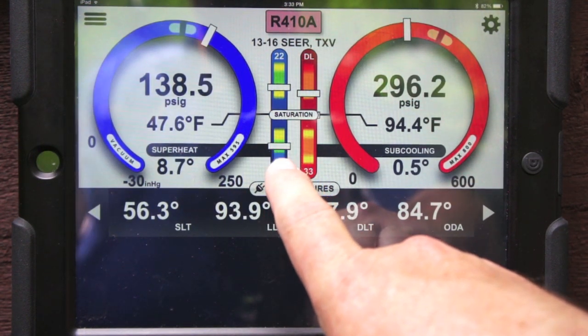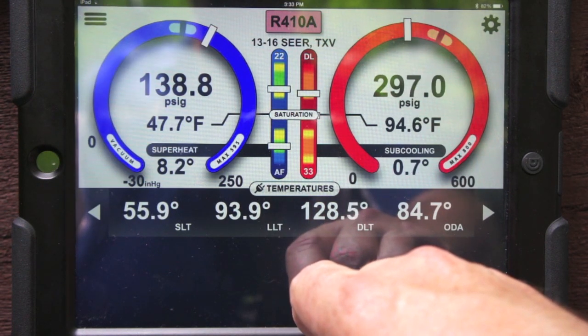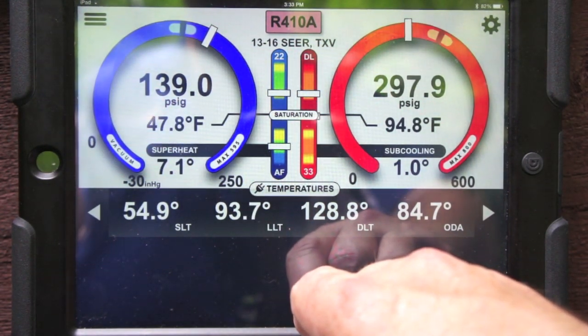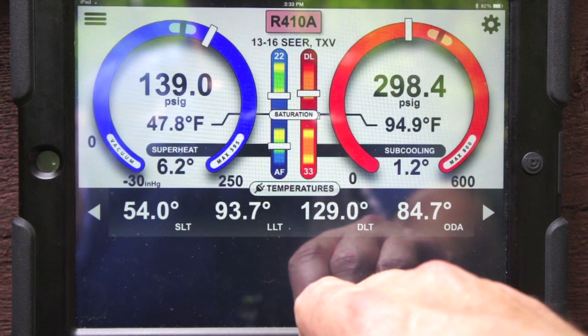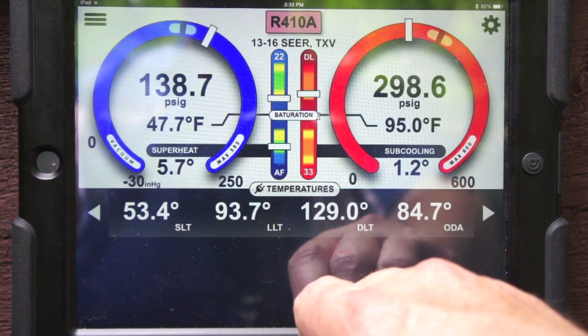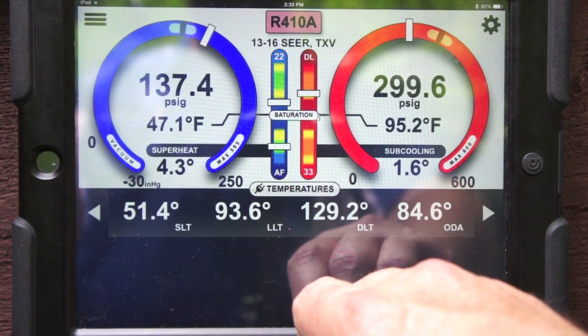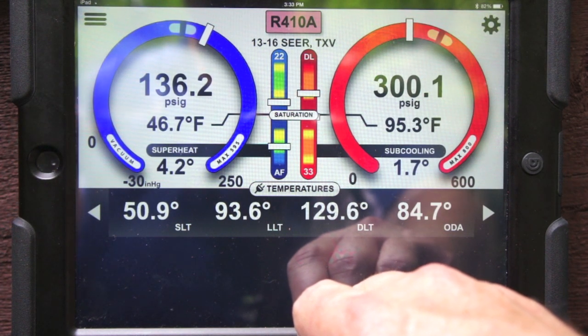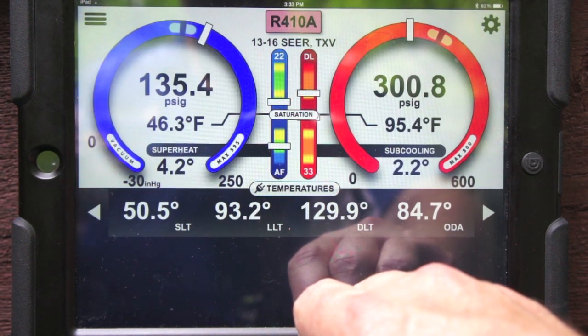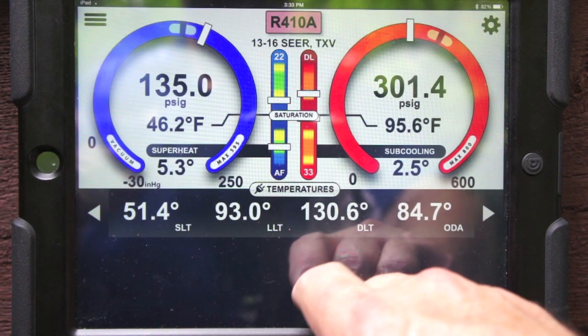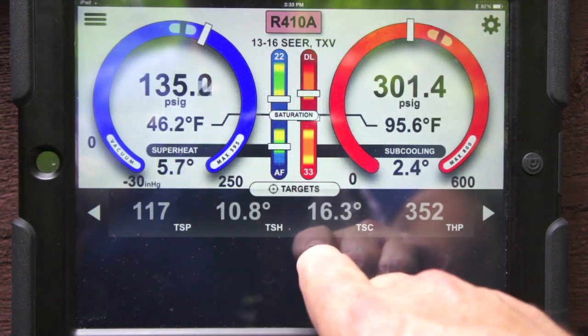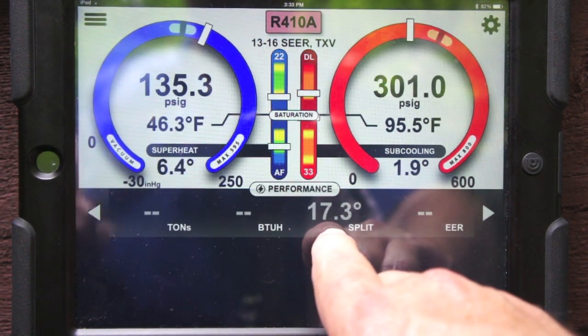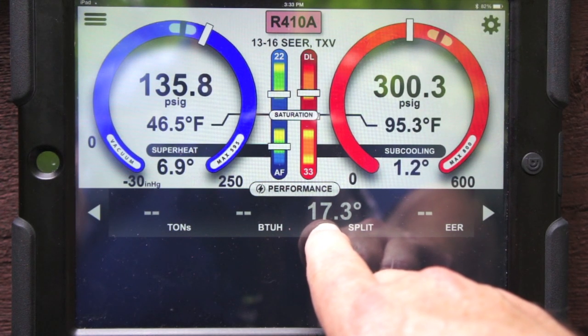If it is in the yellow, that means the airflow is too high. We have enough airflow to charge, and we should continue charging and see if that gets back into spec, because that again is split, and if it's in the green, we're good to go, and we can continue the charging process. So that's just based off of our temperature split, which I'm going to slide over here, which right now our temperature split is 17.3 degrees.